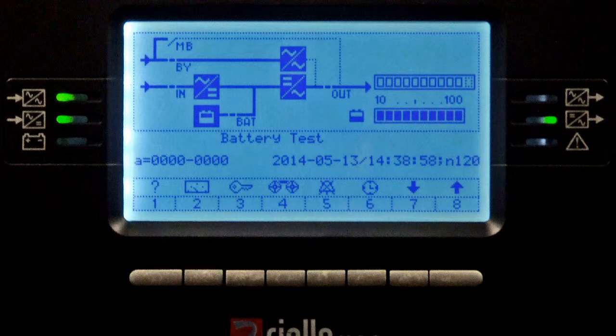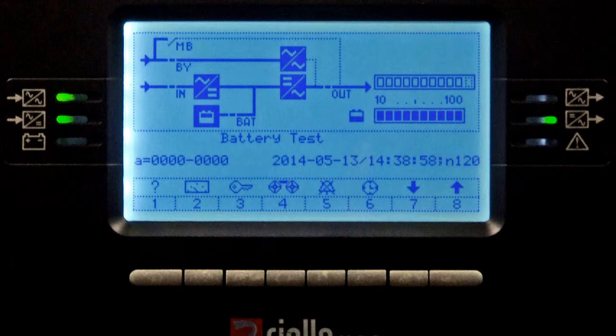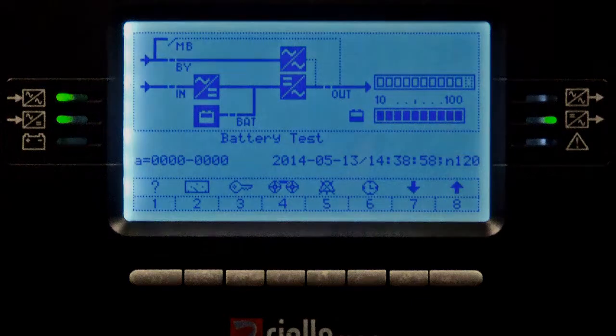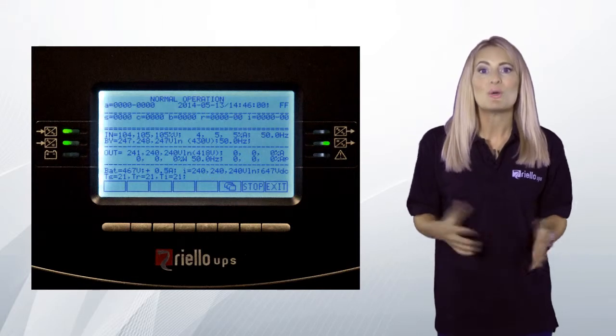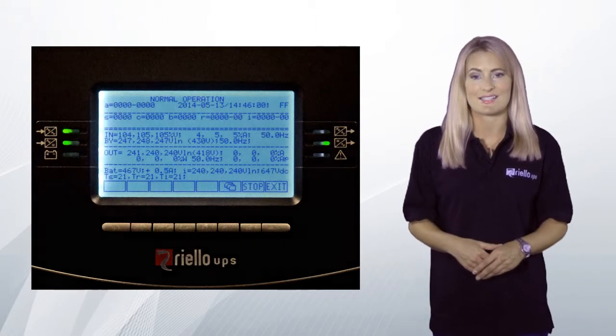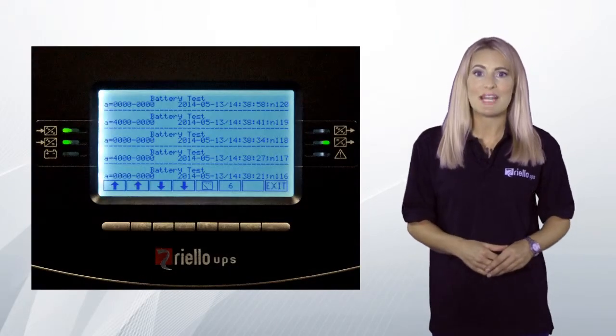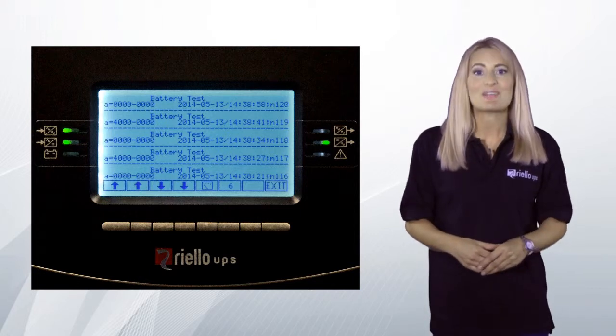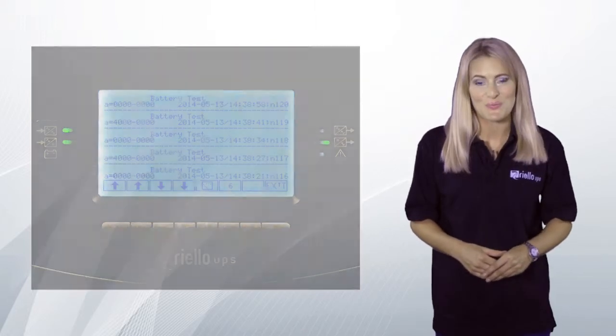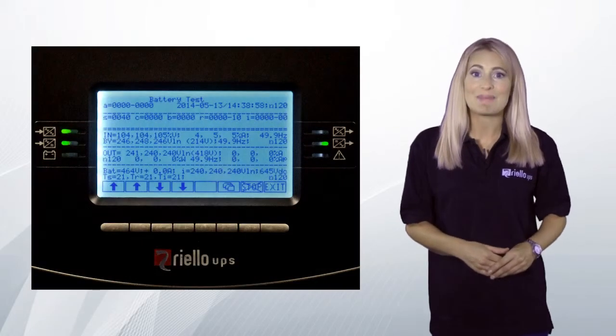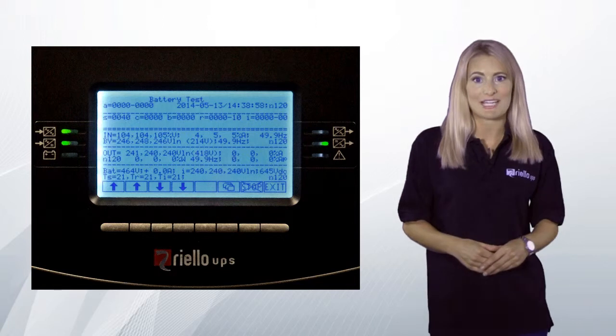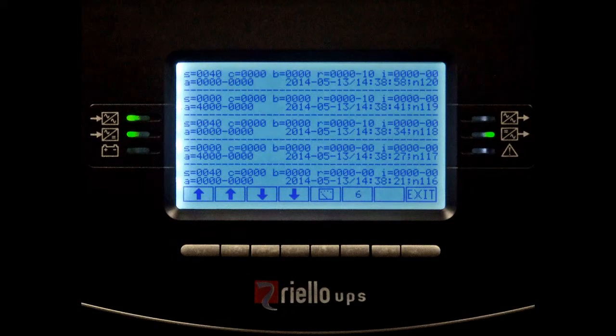Returning to the main menu, pressing button 4 will show the UPS history. The history log comprises 120 operational events, and using buttons 7 and 8, you can navigate through these to see the operational history of the UPS. Pressing button 4 again will provide an overview of the current UPS status. Pressing button 6 will display a summary of the previous 5 history events, which can be navigated through by pressing buttons 1 to 4. Pressing button 6 again will provide additional information about the UPS status at the time of the logged event, and pressing button 6 once more will display UPS internal codes associated with the logged events.